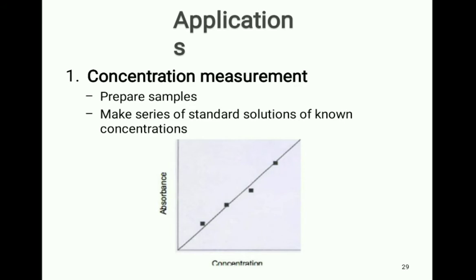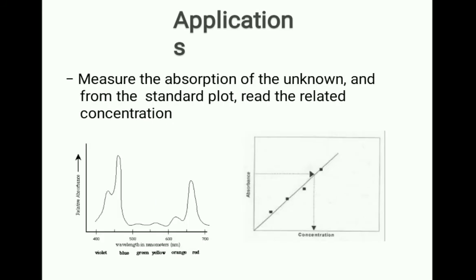Now let us discuss the applications of a spectrophotometer. First: concentration measurement. Prepare a sample and make a series of standard solutions of known concentration. For measurement of concentration we can use a spectrophotometer. As you can see in the graph, when a graph is plotted between absorbance and concentration, a straight line graph is received. Measure the absorbance of the unknown and from the standard plot read the related concentration.